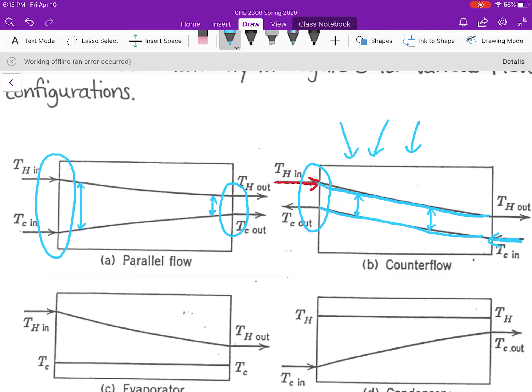This type of heat exchanger gives more uniform heat exchange throughout the entire length, because this driving force or temperature difference is very similar throughout. Whereas here, I have a large temperature driving force at the entrance of the heat exchanger, but a very small temperature driving force at the exit.